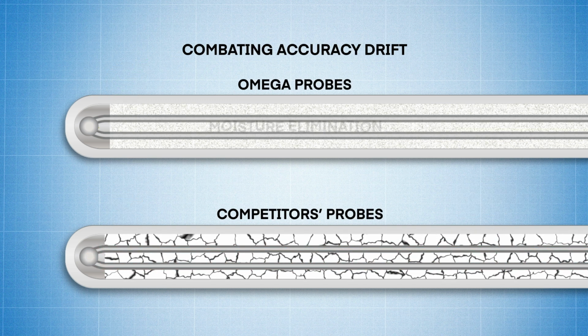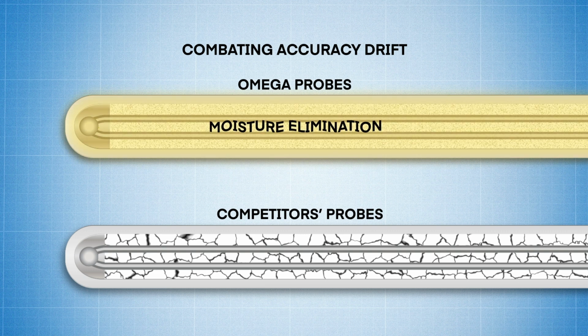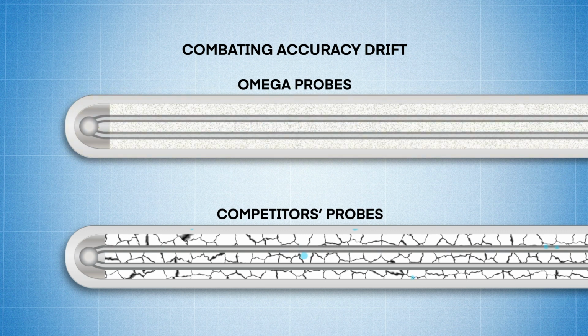Our proprietary manufacturing process eliminates any pre-existing moisture inside the sheath during assembly, because even the slightest bit of moisture inside a probe can expand and condense during heating and cooling, resulting in failure due to a short or accuracy drift.